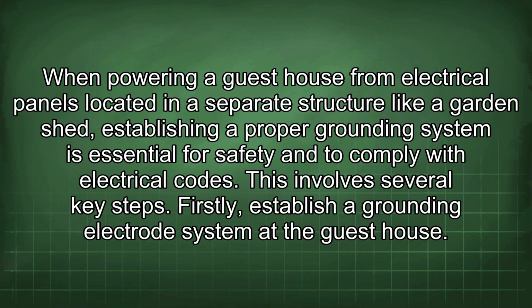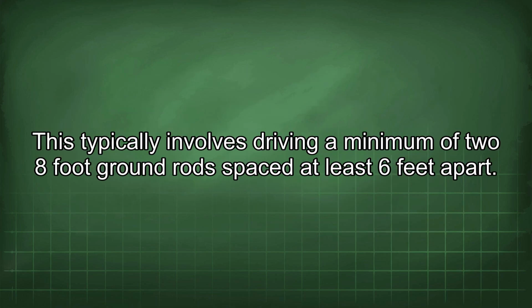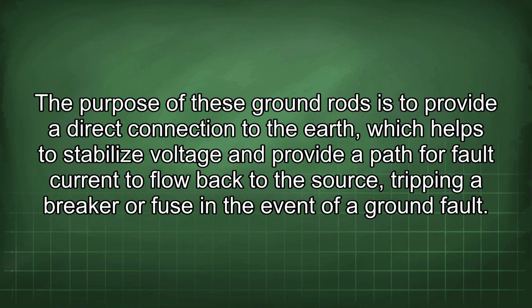Firstly, establish a grounding electrode system at the guest house. This typically involves driving a minimum of two 8-foot ground rods spaced at least 6 feet apart. The purpose of these ground rods is to provide a direct connection to the earth, which helps to stabilize voltage and provide a path for fault current to flow back to the source, tripping a breaker or fuse in the event of a ground fault.